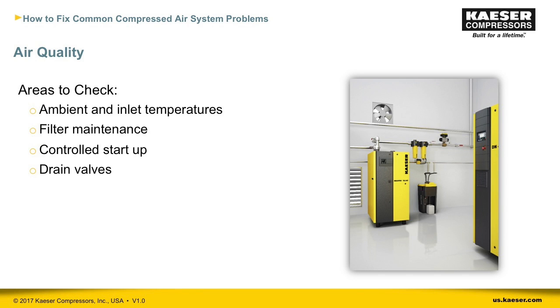Drain valves. They should be on tanks, filters, dryers, and low points in the piping system. Are they functioning properly or due for service? Many have a test button that you can use to confirm they are working. Use zero-loss automatic drains to prevent compressed air loss.